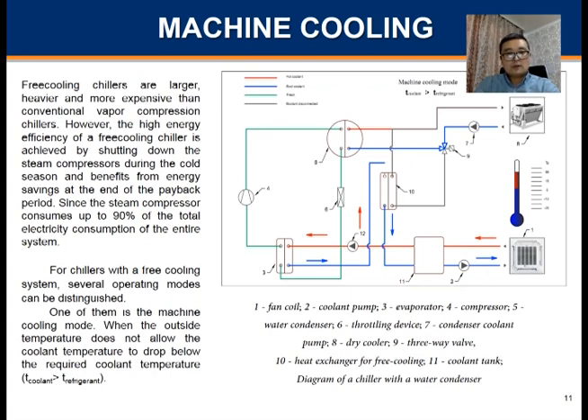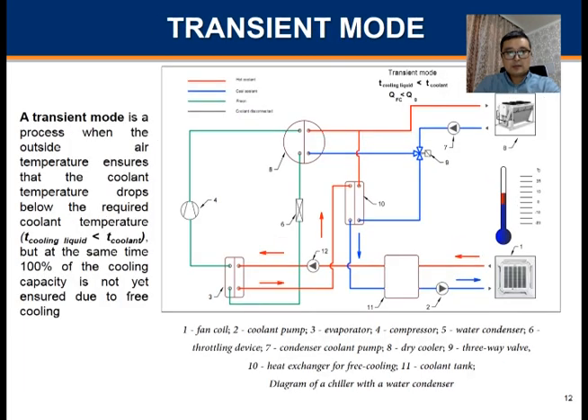For chillers with a free cooling system, several operating modes can be distinguished. One of them is the machine cooling mode, when the outside temperature does not allow the coolant temperature to drop below the required temperature. A transient mode occurs when the outside air temperature ensures the coolant temperature drops below the required temperature, but at the same time 100% of the cooling capacity is not yet ensured by the free cooling.